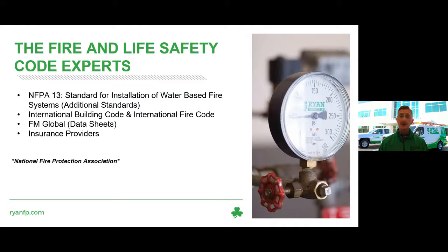Keep in mind, there are hundreds of NFPA standards. So if you have flammable liquids, for example, that's going to take us to a different standard, NFPA 30 for code reference. International Building Code and Fire Code are also very important. FM Global has their own code book, or what they like to call data sheets, so we kind of set NFPA off to the side and go strictly with their data sheets.